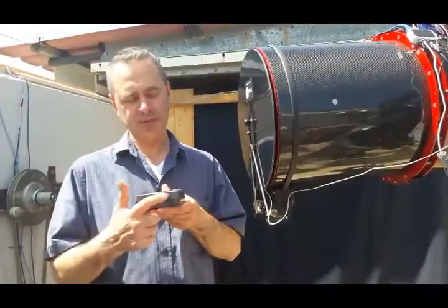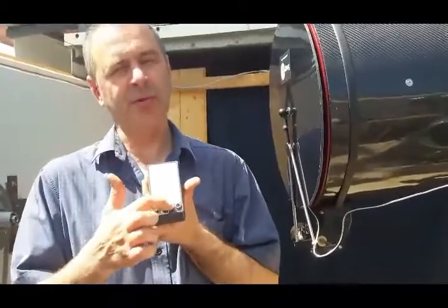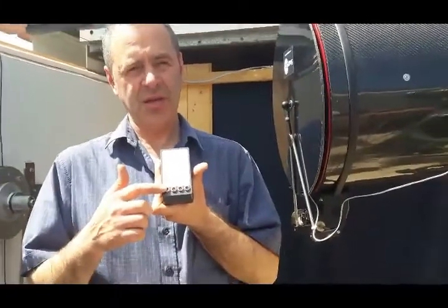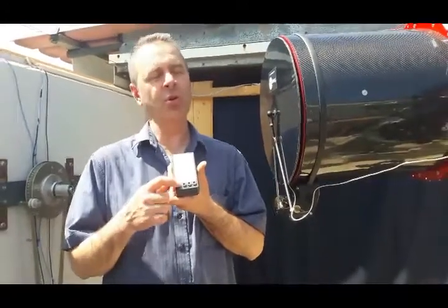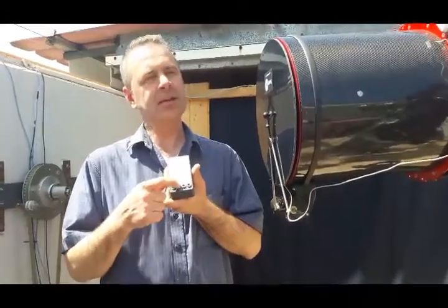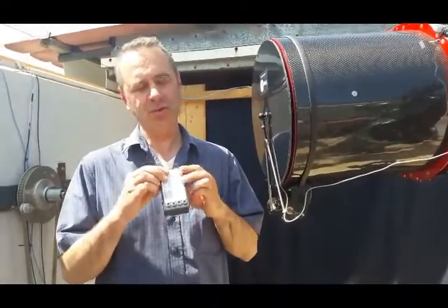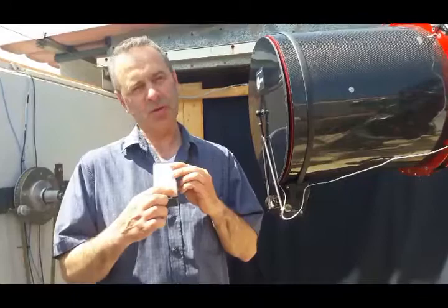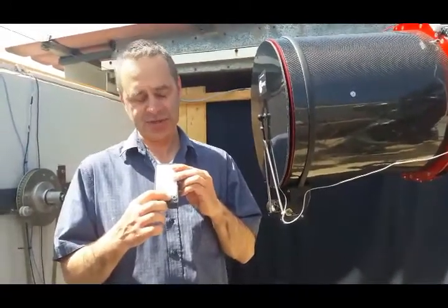The power must be connected to this connector, and you have 4 output channels. Two output channels will be used by SNAPCAP — one for opening and closing, and the other for switching the light on and off. So if you buy this control option, you will have 2 free relay contacts left for your other accessories.